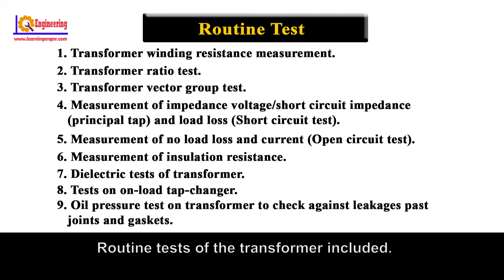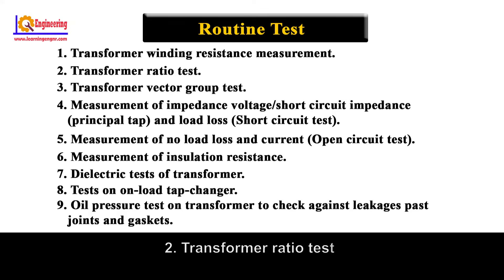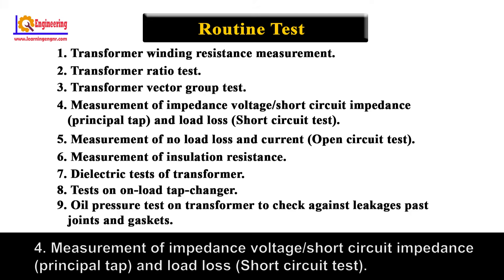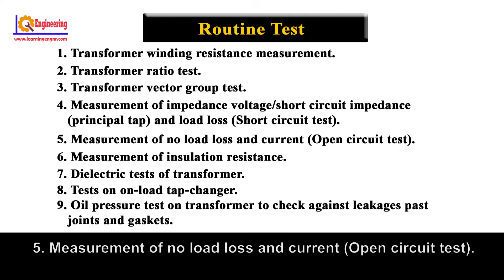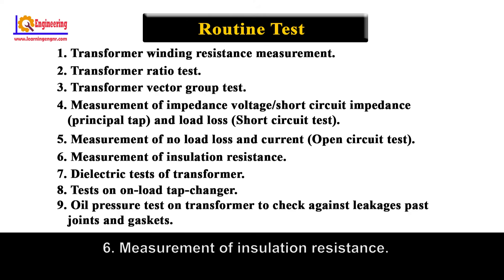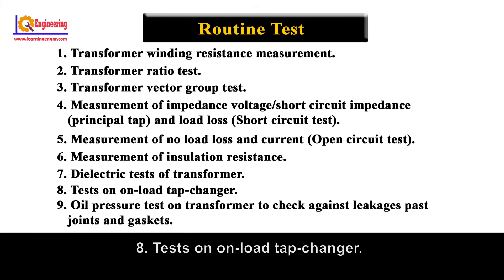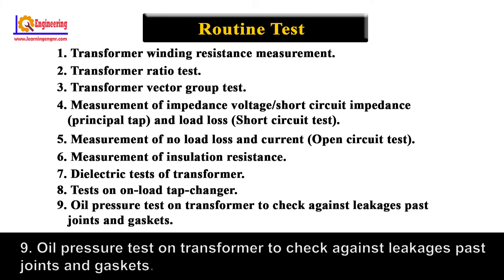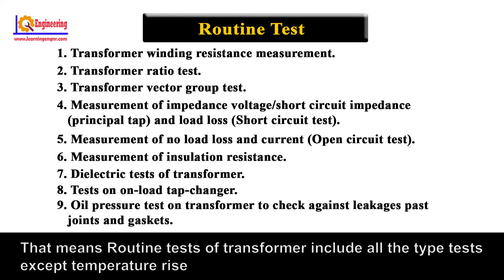Routine Test of the Transformer includes: Number 1, Transformer Winding Resistance Measurement; Number 2, Transformer Ratio Test; Number 3, Transformer Vector Group Test; Number 4, Measurement of Impedance Voltage or Short Circuit Impedance at Principal Tap and Load Loss (Short Circuit Test); Number 5, Measurement of No Load Loss and Current (Open Circuit Test); Number 6, Measurement of Insulation Resistance; Number 7, Dielectric Test of Transformer; Number 8, Test on Load Tap Changer; Number 9, Oil Pressure Test on Transformer to check against leakages past joints and gaskets. That means Routine Test of Transformers includes all the type tests except temperature rise and vacuum tests.